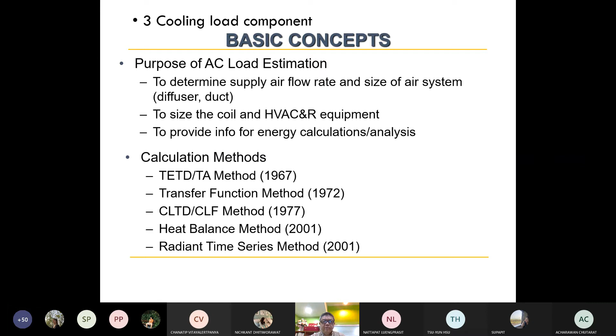The major steps in load estimation: you have to determine the indoor and outdoor design condition, estimate the thermal properties for the envelope components, determine zoning, space, and perform the area takeoffs, and estimate space sensible and latent loads. The sensible load will help you design the airflow of the rooms.